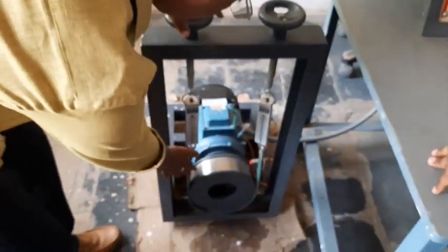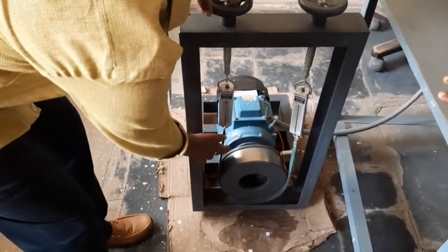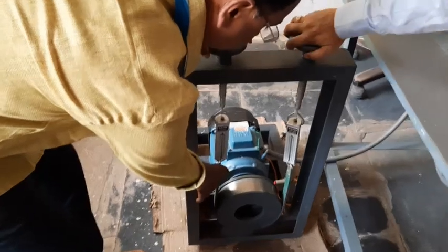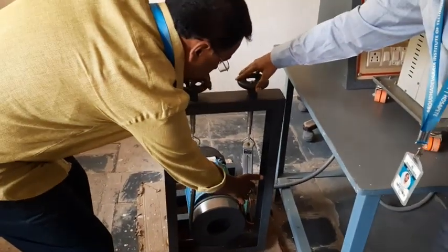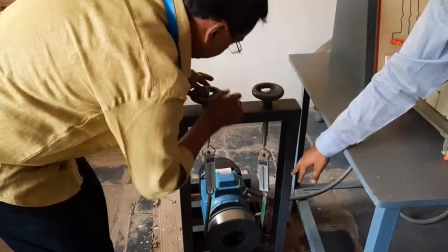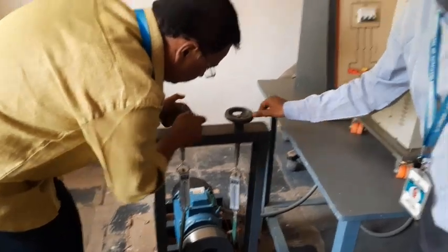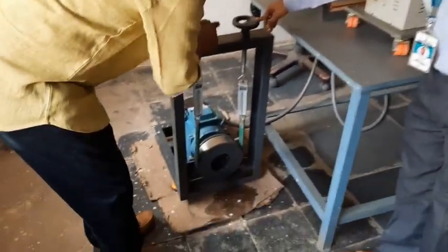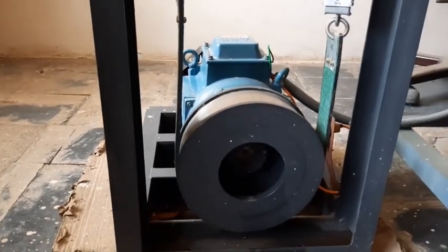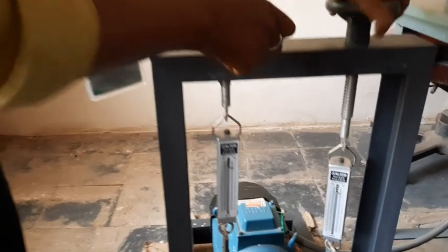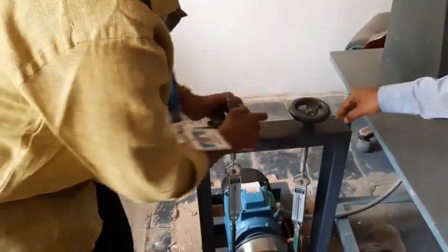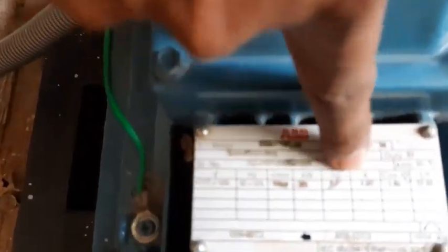Now tighten the motor pulleys with a belt drive. This is called the blocked rotor test because the rotor is blocked with the belts and pulleys. Totally tighten this. After tightening, 4.6 ampere is the full load rated current of the induction motor. So we need to apply 4.6 ampere for that purpose.